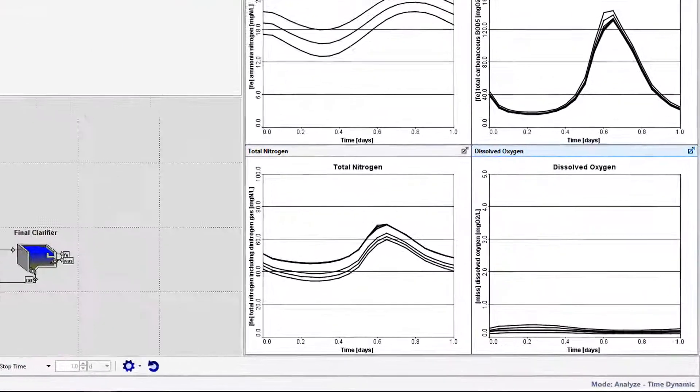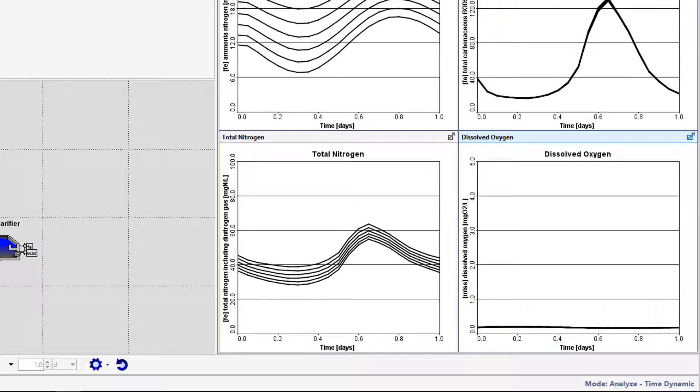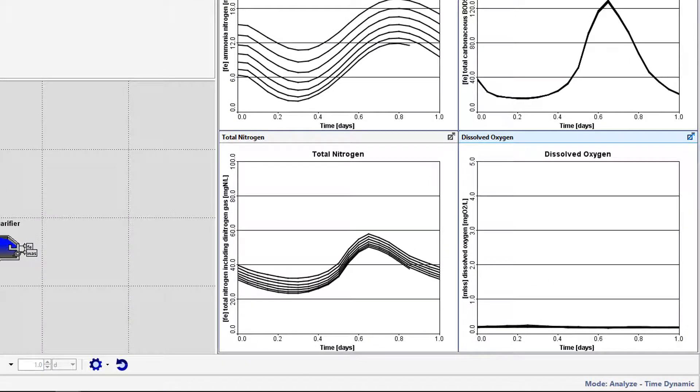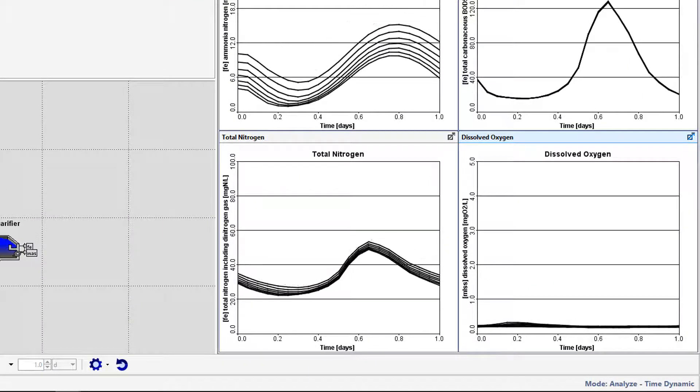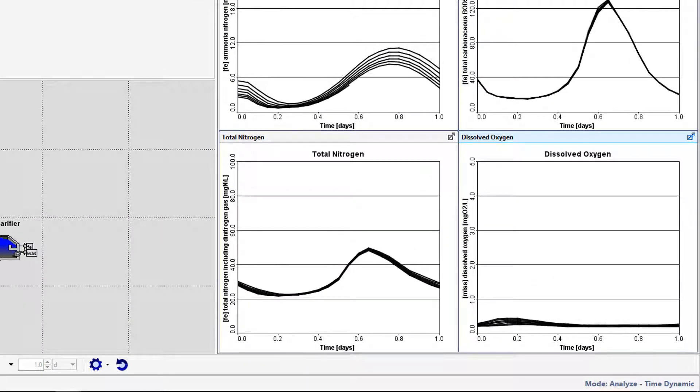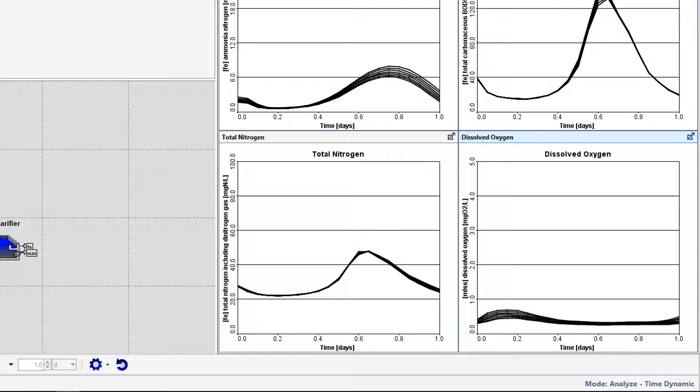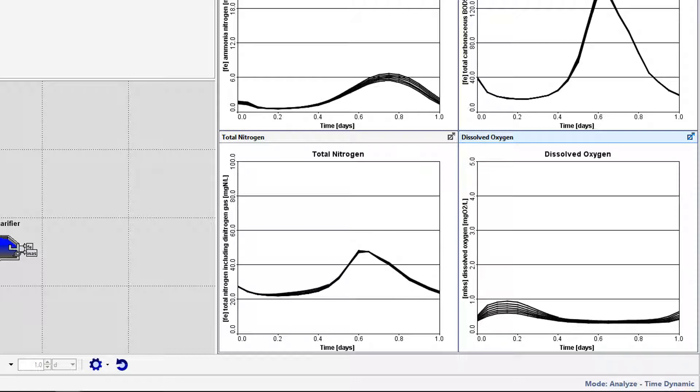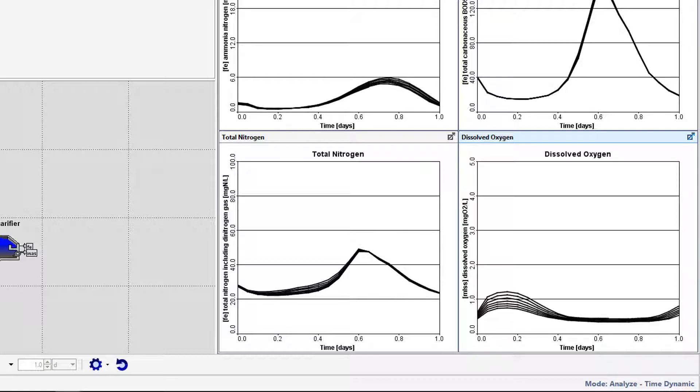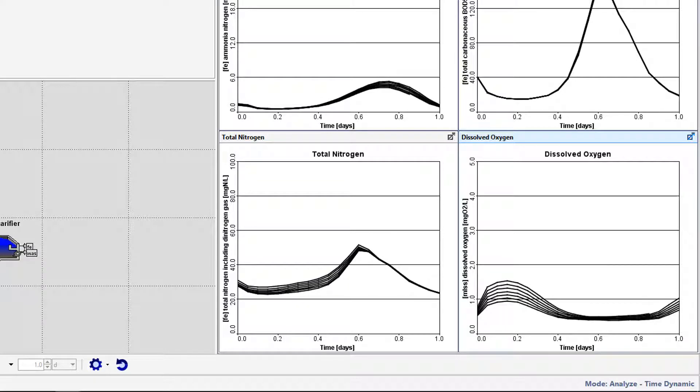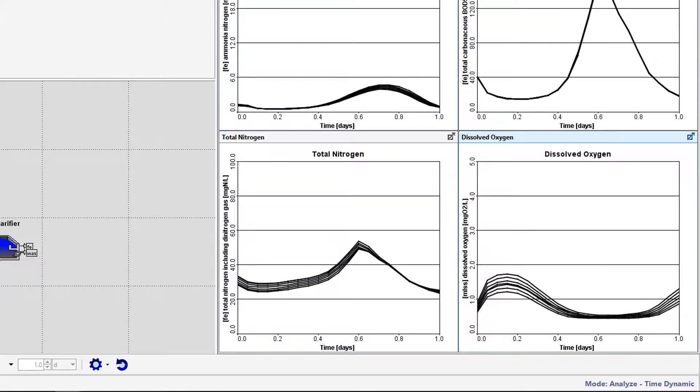Looking at the DO graph, you will notice that for increasing air flows, the DO concentration increases, in addition to fluctuating with time due to the sinusoidal influent flow and load patterns.